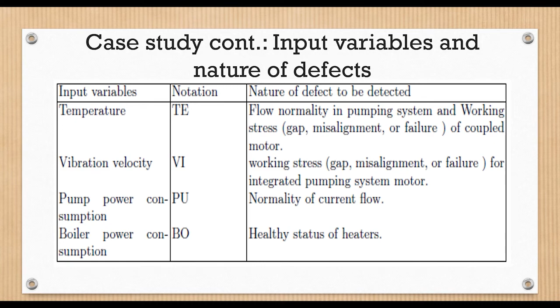General and specific expert data were collected from 2 hospitals, and experiments were conducted at one of them. The autoclave's main critical components and available empirically based thresholds of physical condition parameters were highlighted, and only 4 metrics, temperature, vibration, pump and boiler power consumption, are considered as input variables of our fuzzy expert system to prioritize maintenance activities.